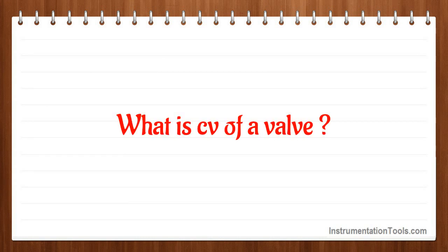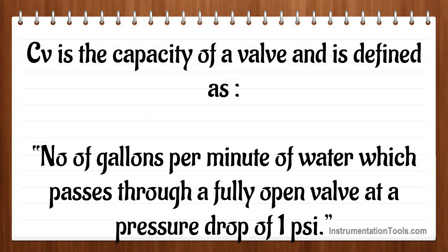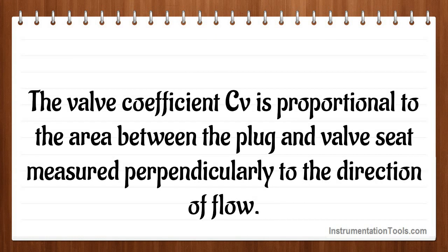What is CV of a valve? CV is the capacity of a valve and is defined as the number of gallons per minute of water which passes through a fully open valve at a pressure drop of one psi. The valve coefficient CV is proportional to the area between the plug and valve seat measured perpendicularly to the direction of flow.